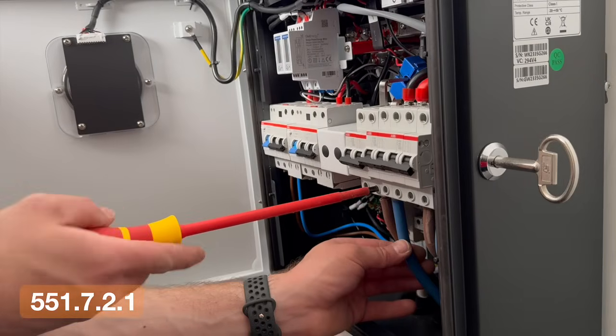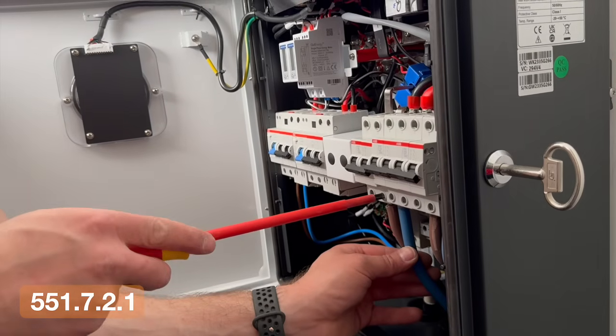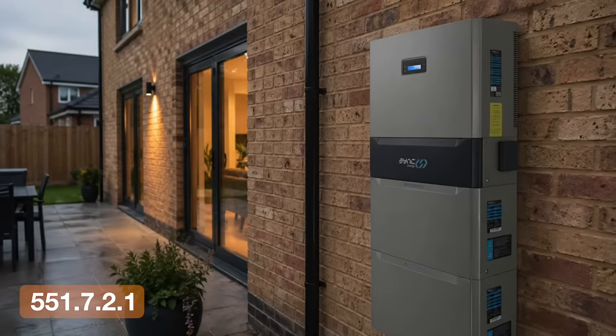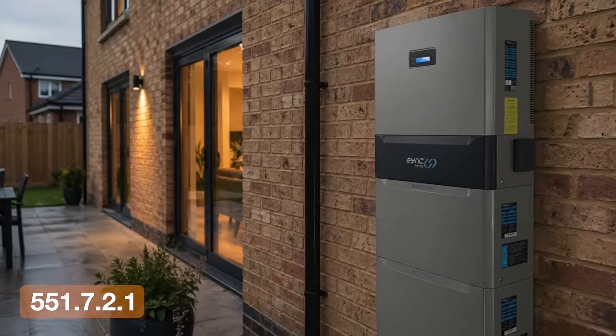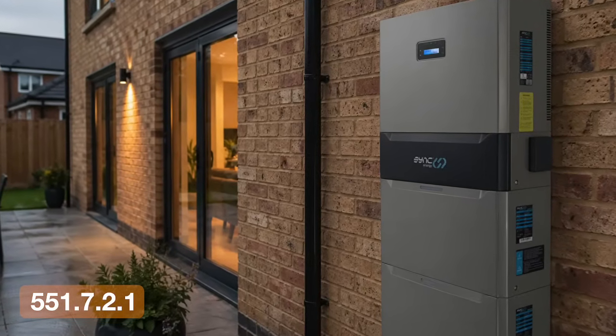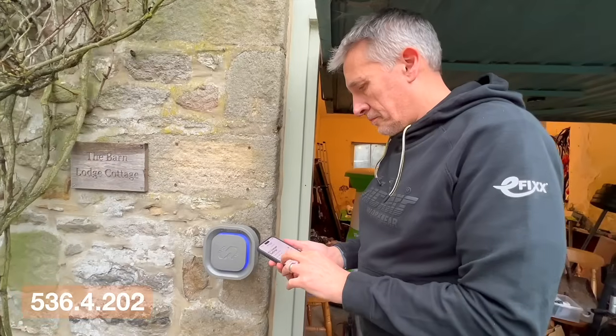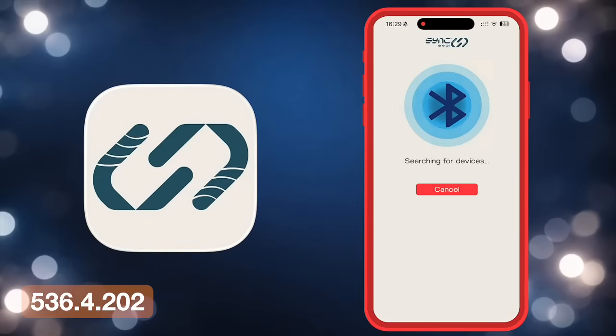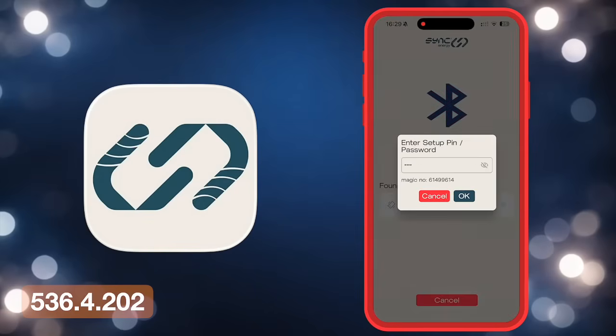Regulation 551.7.2.1 now requires that generation sets are connected on the supply side of the protective device for the final circuits. So in simple terms, generation needs to be connected upstream of the circuit it is supplying. And importantly, this includes batteries, which are now treated as a generating set in this context, not just a load. There are also supporting changes around this idea. Regulation 536.4.202 has been redrafted and now includes coordination between protective devices, assemblies, and load control, such as load curtailment.